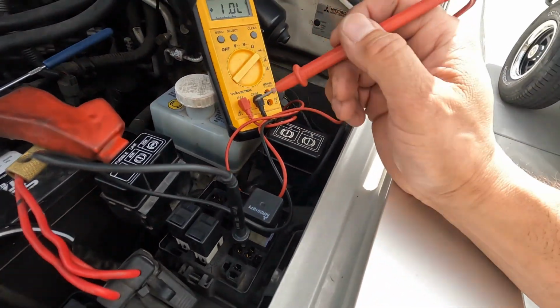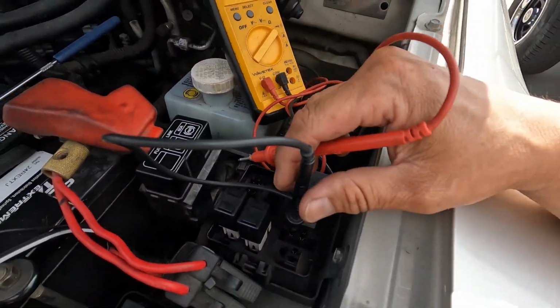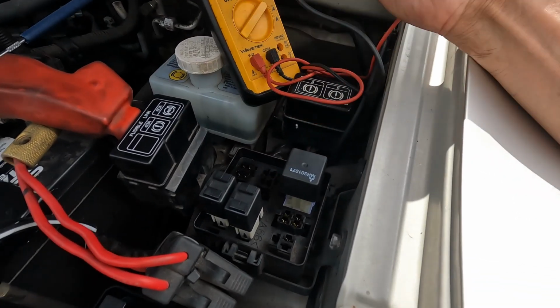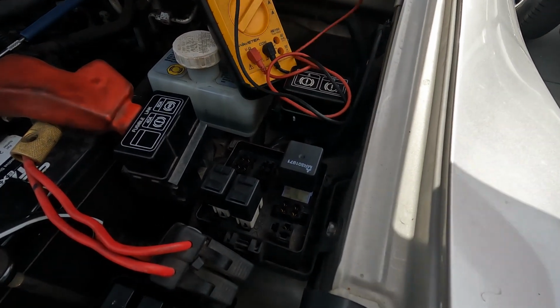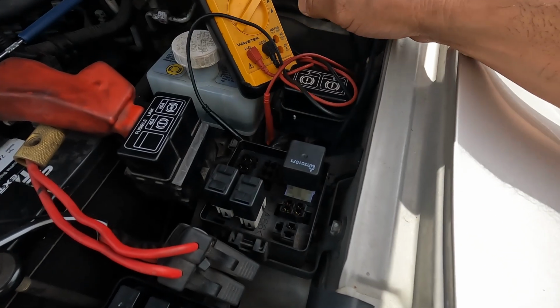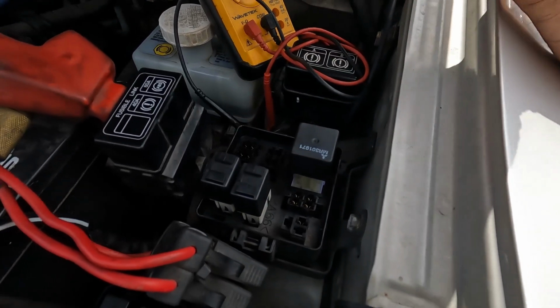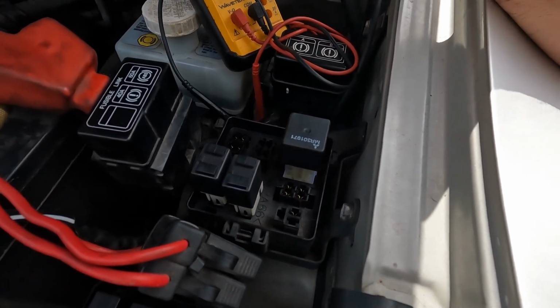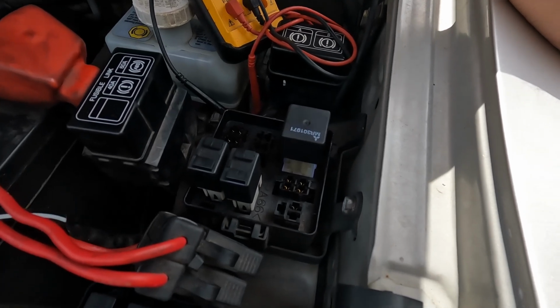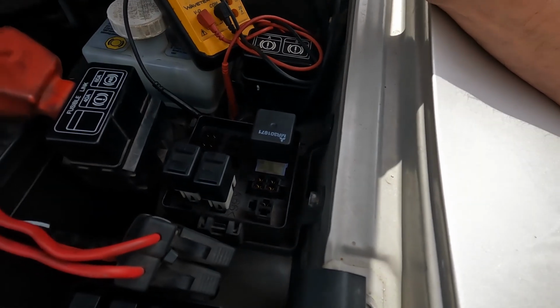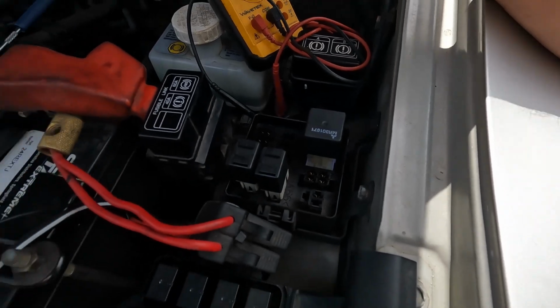Now, when you're checking a ground this way, I don't really like checking grounds this way, especially on a circuit that's a high current type circuit. Not very high current, but there are some amps going through there. The best way to check it is to actually put the circuit under some kind of load.